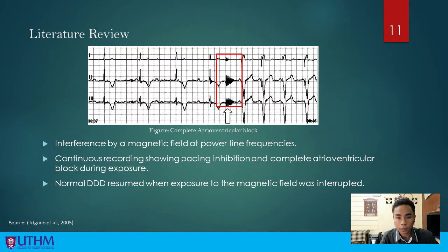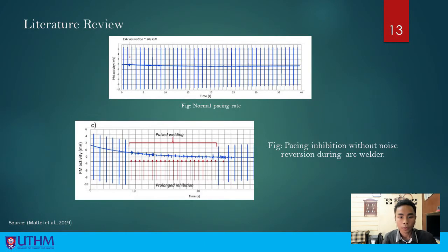For example, here, due to the interference of magnetic field at power line frequency, pacing inhibition occurred and complete atrioventricular block was recorded during exposure. But the normal setting program of DDD resumed when exposure to the magnetic field was interrupted. For this slide, we can see the figure above is the normal pacing rate. For the figure below, we can see the pacing inhibition without noise reversion during the arc welder activation, where the cable of the welding system was placed over the shoulder of a phantom.